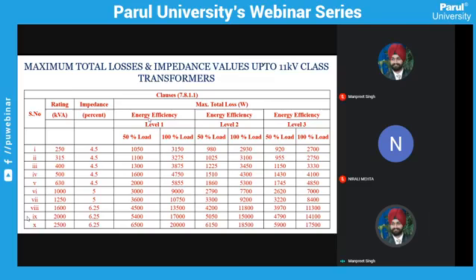For example, a 250 kVA transformer at efficiency level 1, at 50% load, should have a loss of 1050 watts (about 1 kilowatt), and at 100% load, 3.15 kilowatts. If we take a more energy efficient transformer, the loss reduces at both 50% and 100% load. At level 3, the loss is further reduced.